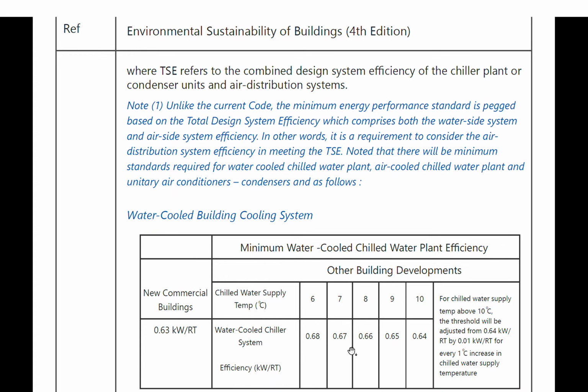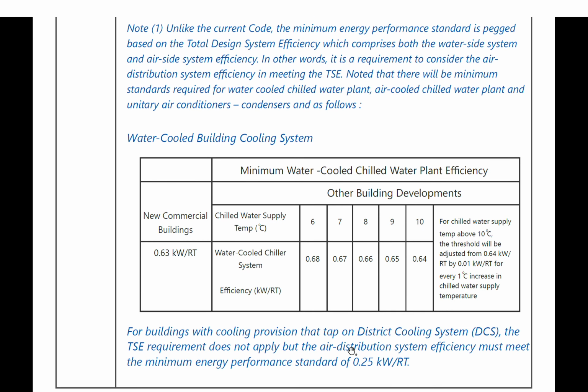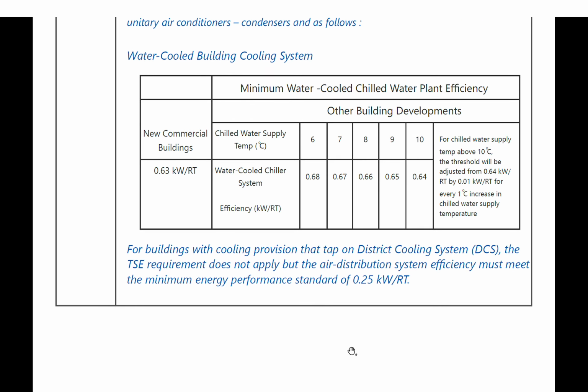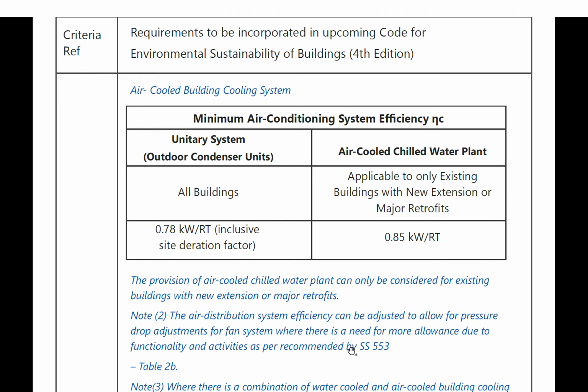So for some of the water cool buildings, right, there are codes developed, like chilled water temperature should be at about 6, 7, 8 to 9 to 10 degrees, and then the water cooled chiller system efficiency should be approximately 0.68 if it's an old building to 0.64, and if it's a new kind of building, it should be about 0.63 for the new kind of cooling efficiency. So air cool also has a certain efficiency that we need to meet. For air cool, just on the unitary systems, it should be about 0.78, and for air cool plant, for new or existing, about 0.85. That's the efficiency, and then it complies with SS553.